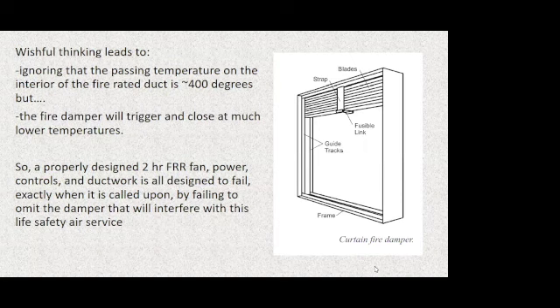It's going to close when we reach that threshold temperature. But when we're dealing with life safety systems, we know that we want it to work during the fire. And if you're familiar with the fire resistance test standard, that is our benchmark, ASTM E119, or its counterpart UL263, we know that the passing temperature on the unexposed side is around 400 degrees. It's a threshold above ambient, assuming ambient is around 70, 75 degrees in the test lab that day.